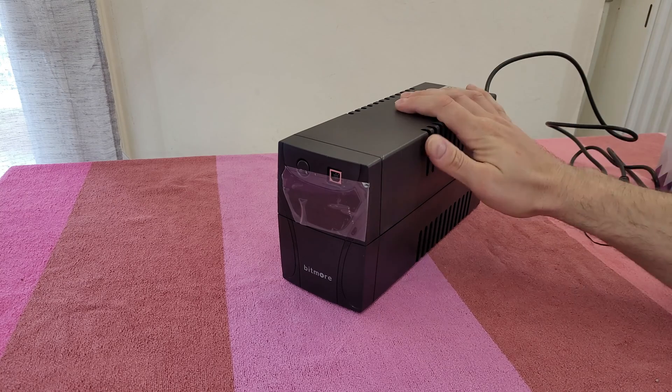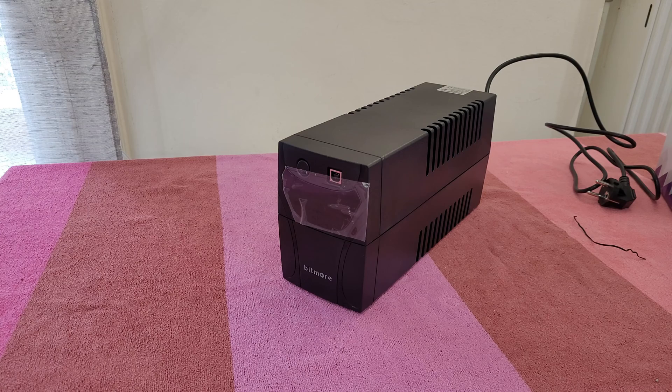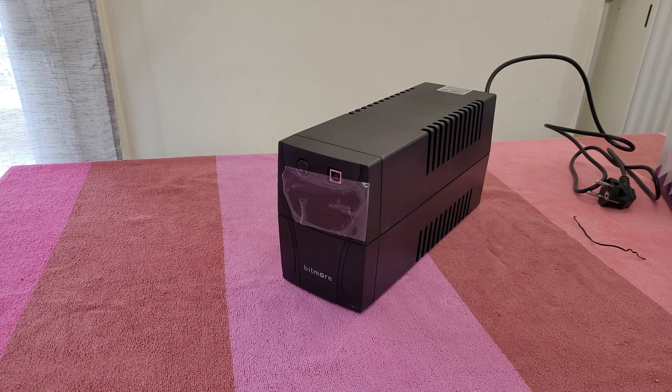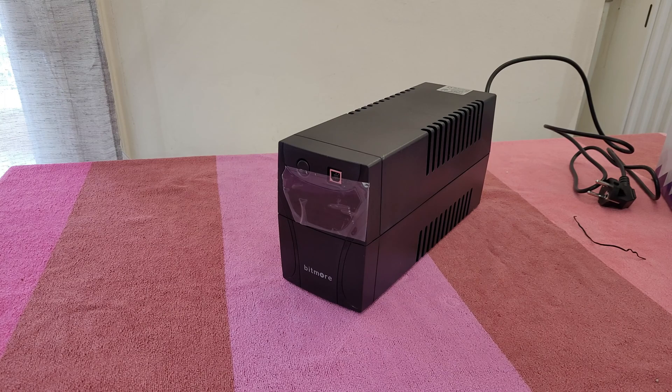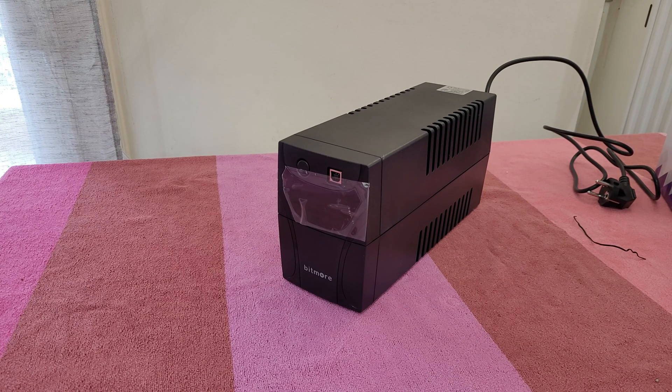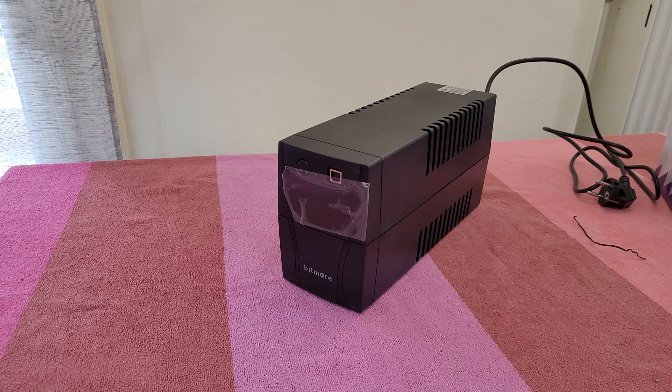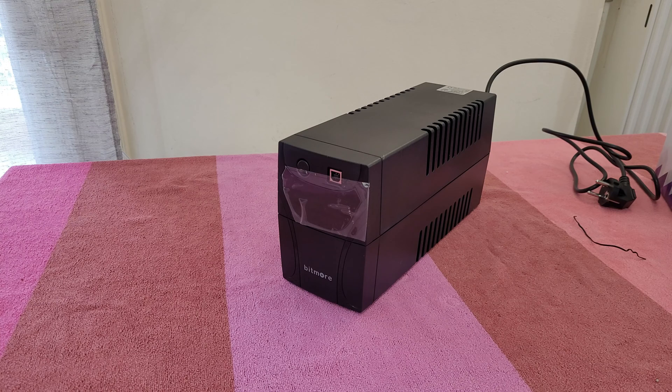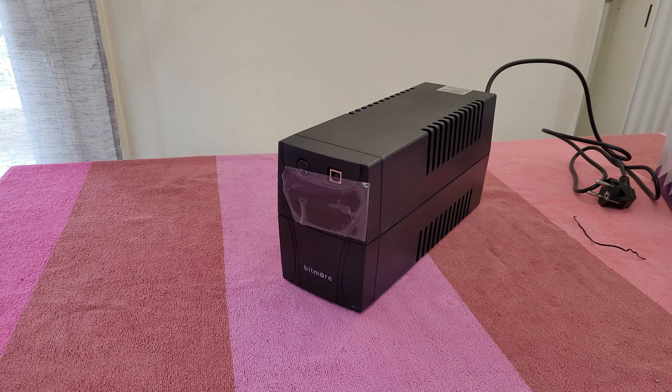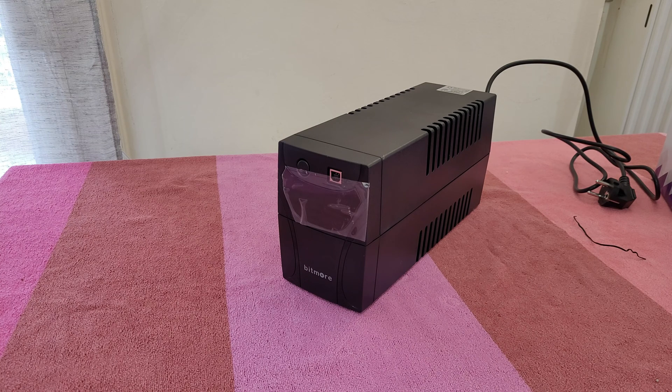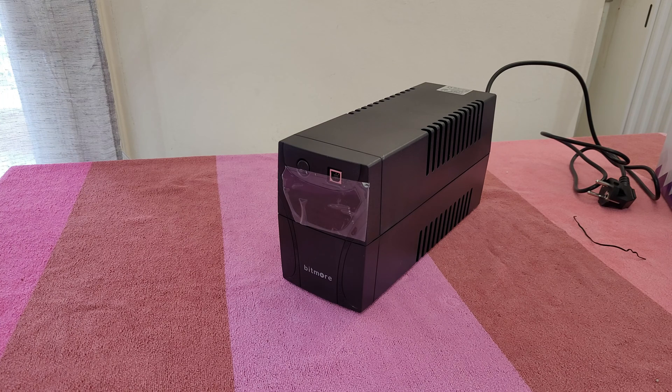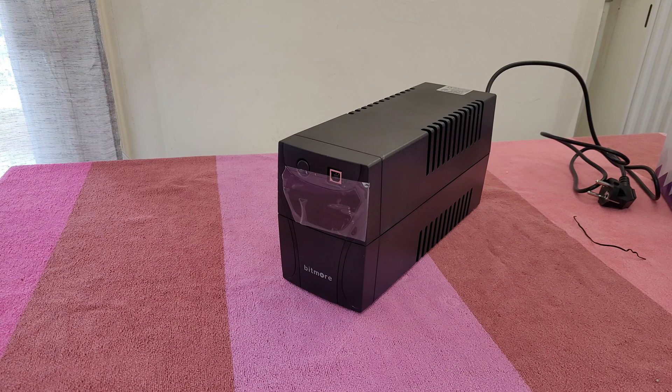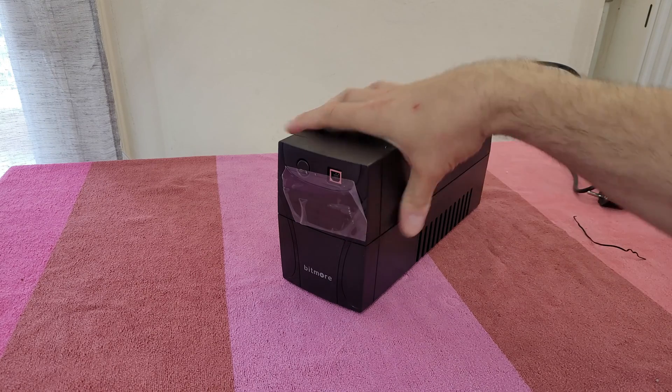This unit is 480 watts with a 12 volt, 9 ampere hour battery. Recharge time after complete discharge takes 6 hours to 90 percent. Transfer time typically goes from 2 to 8 milliseconds and 10 milliseconds maximum. When on backup, it sounds every 10 seconds; when low battery, every one second; when overload, every 0.5 seconds; and when there's a failure, it will continuously sound. It has full protection: discharge, overcharge, and overload protection.